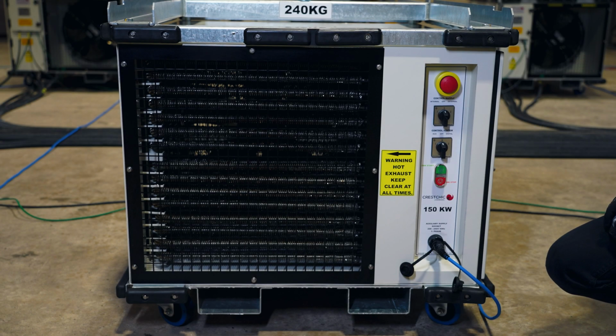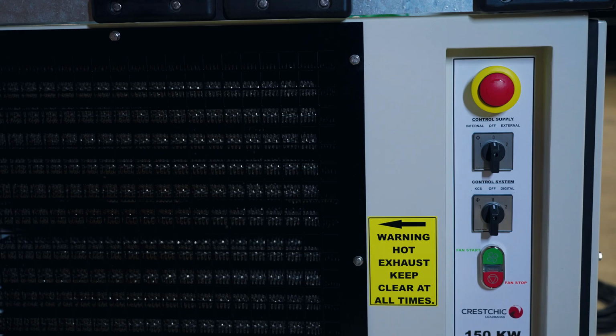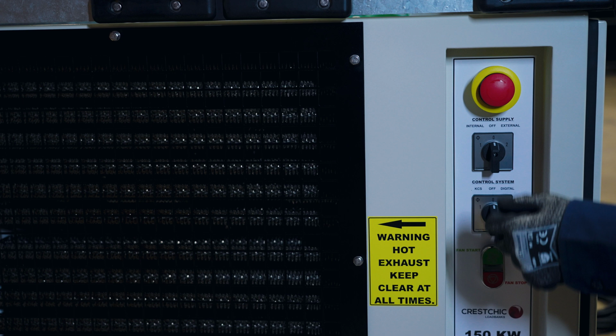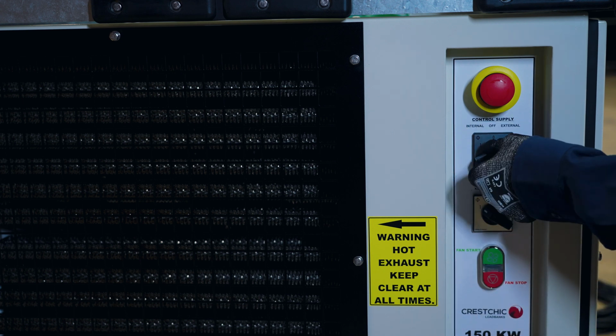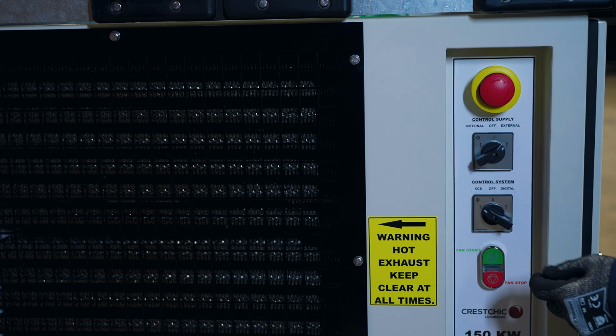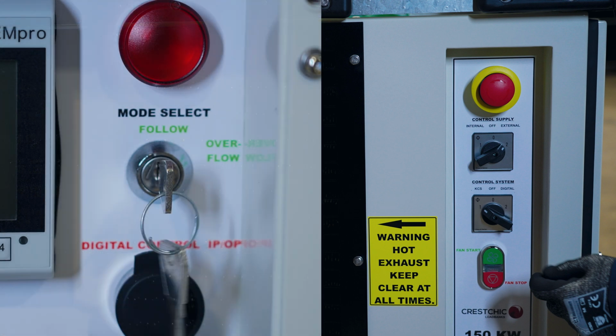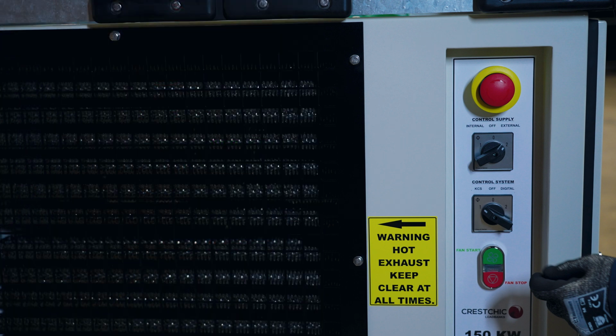In this demonstration, we have a 3-phase 415 volt supply to the load banks. We check the emergency stop is out. We are using an auxiliary supply for the load banks control system. Therefore, we switch the control supply switch to external. Select the loading mode. In this case, we will use follow. Then select the controller type, which is the KCS controller. This should be completed on all load banks.